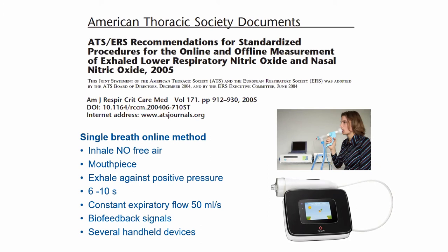So there has to be a filter that filters the NO out of the air so that no particle of NO will be in the air you inspire. And then you exhale against a small resistance. Why this? Because this will close your soft velum, and then only the air that comes from the lower airways will go out into this analyzer and be analyzed.